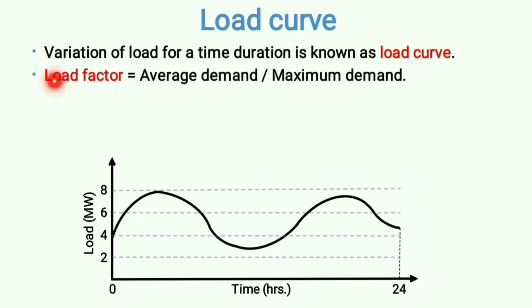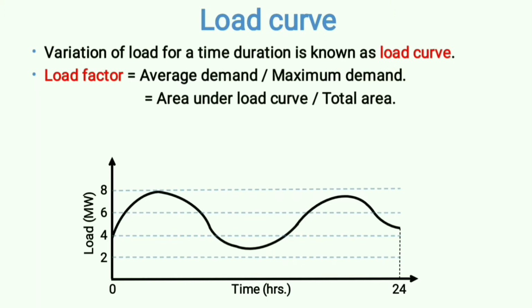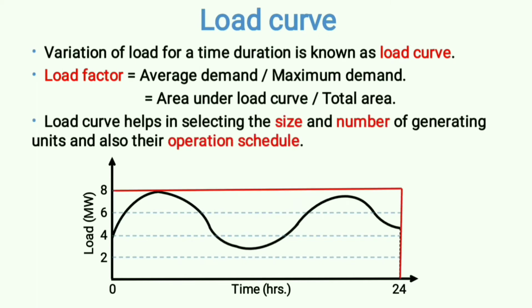For example, load factor is nothing but average demand by the maximum demand. This load factor can also be written as area under the load curve by total area.